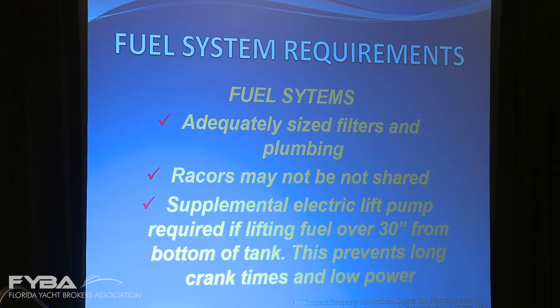A really tricky issue, especially on bigger boats where the tanks are some distance from the generator: if you have to lift the fuel more than 30 inches, it's really necessary to have a supplemental fuel pump, because 30 inches is pretty much the practical limit for lifting fuel with just the engine's lift pump. This causes long crank times and typically low generator output. The generator won't carry quite as much load, but the generator technician comes by and says, 'I can't find anything wrong with the generator.' This is particularly something you'll run into during a refit.